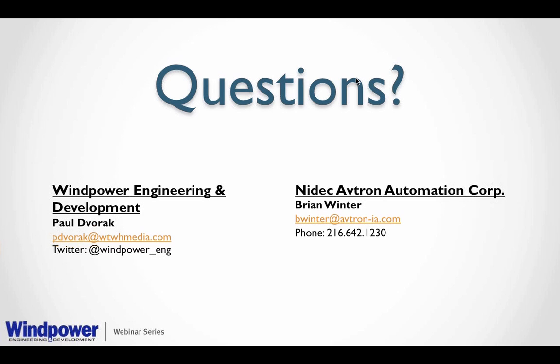Okay. All right, Brian. So finally, the audience has really popped up here. Let's see, a couple of the questions. GE troubleshooting for a GE pitch system suggests checking blade positioning and then unplugging the encoder for 15 seconds, then replugging it to see if values stay the same. Does this help verify that the encoder is bad? Any other solutions would be helpful.